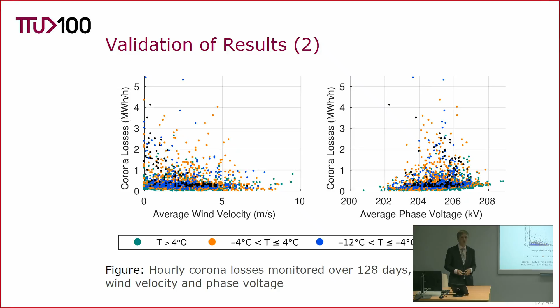Now we can take a look at longer term monitoring data, where we can see the measured corona losses and their dependence on the same quantities we observed earlier. So dependence on average conductor temperature and relative humidity, and also dependence on average wind velocity and phase voltage. So we can see that in general the dependence of corona losses on these quantities is similar to what we saw from the previously published study.